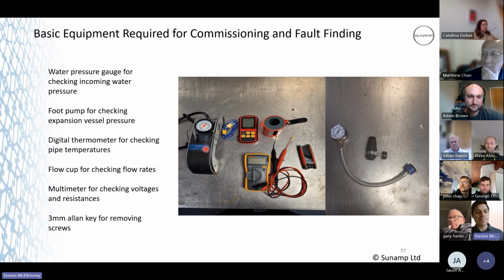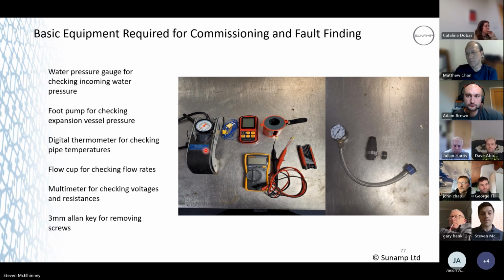Foot pump for checking expansion vessel pressure. We do recommend that the customer gets that vessel repressurized every 2 to 3 years, because all that's in there is an air charge, which is going to dissipate over time. So if you lose your air charge, you lose that expansion quality, which means you could be introducing water hammer to the system as well.